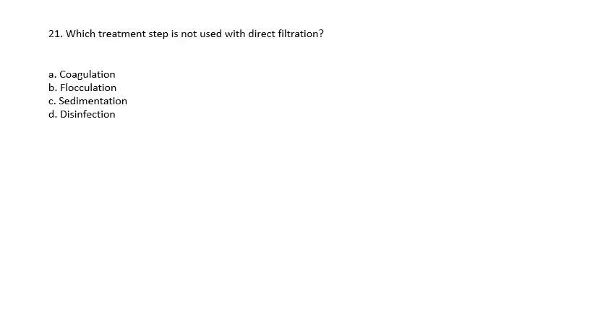Question 21: Which treatment step is not used with direct filtration? Coagulation, flocculation, sedimentation, or disinfection? The answer is sedimentation. When doing direct filtration, you generally don't do sedimentation.